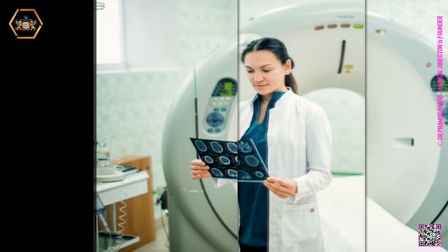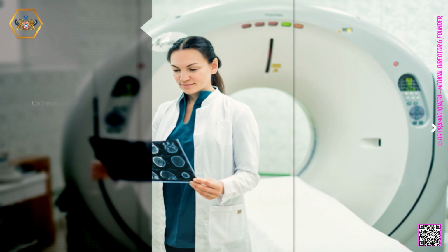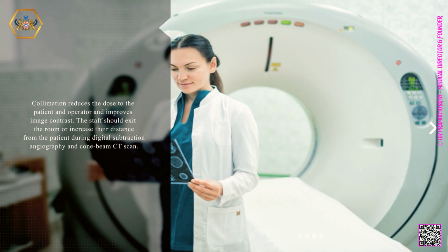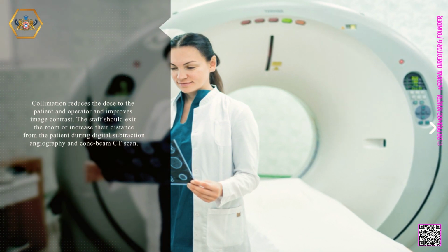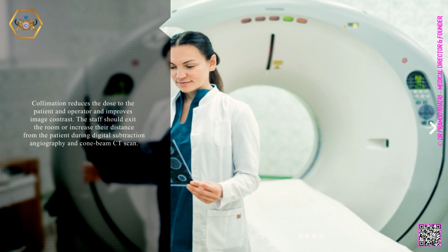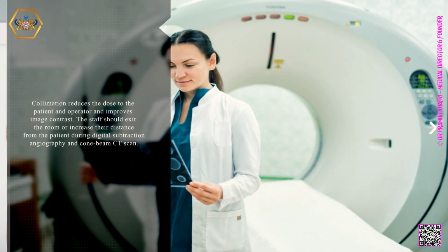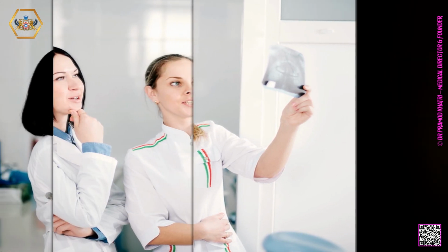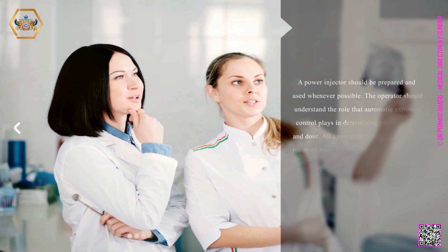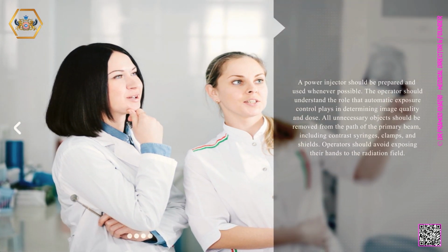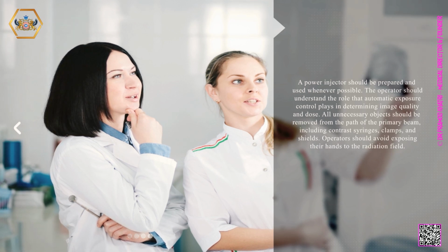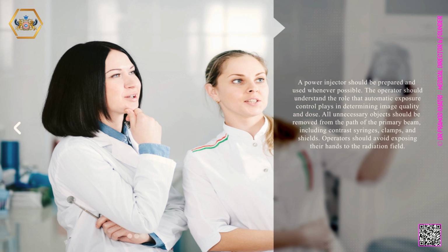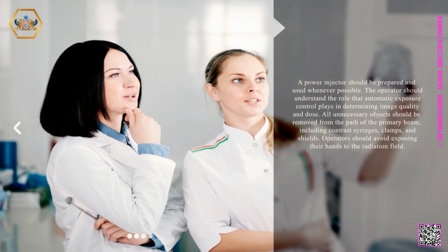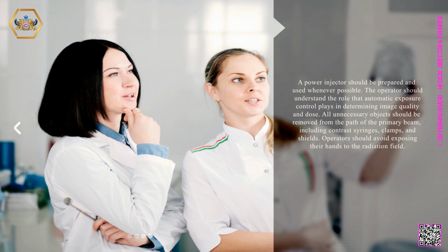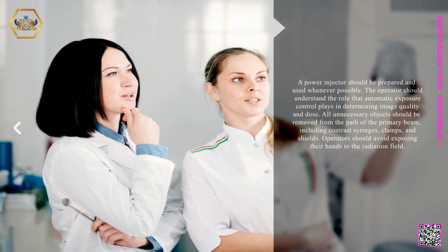Collimation reduces the dose to the patient and operator and improves image contrast. The staff should exit the room or increase their distance from the patient during digital subtraction angiography and cone beam CT scan. A power injector should be prepared and used whenever possible. The operator should understand the role that automatic exposure control plays in determining image quality and dose. All unnecessary objects should be removed from the path of the primary beam, including contrast, syringes, clamps, and shields. Operators should avoid exposing their hands to the radiation field.